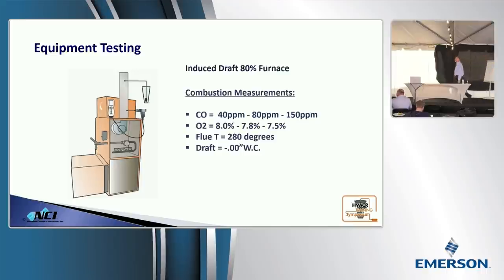John: Hey, when you're setting up this test, do you do it from point of ignition or do you have to reach steady state? We measure from the second it lights till the second it goes off. So John's question was, do we test when it reaches steady state, when it's warmed up, or do you let it continue to test the whole thing? We test the whole operation. We test the first 60 seconds of operation, which is light off. We test three readings during the run cycle. So that's usually from 5 minutes on. So 5 minutes, 7 minutes, 10 minutes. And then we also test for 60 seconds after shutdown.